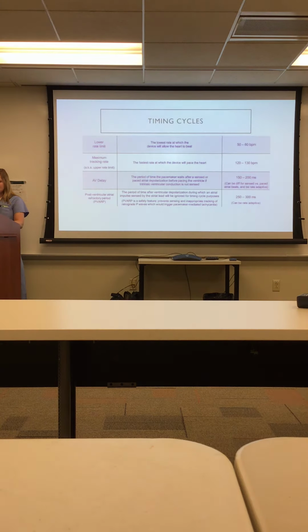Okay, so that is getting into the next one with timing cycles, so we'll briefly go over that, just to make this terminology familiar to you. The lower rate is the lowest rate the device will allow the heart to beat. Typically we program them to 50 or 60 beats per minute. If you're VVI paced and you're just pacing along, you'll be able to measure the pace beat out every 60 beats a minute. You'll see that pacer spike, about 5 boxes, march out every single time. Now, if a sensed event comes in before that, then the paced beat is withheld. You're not going to see it because the rate is coming in, maybe in the 70s in that case. So that's your lower rate. Anytime it falls below, it's always going to deliver a pace.